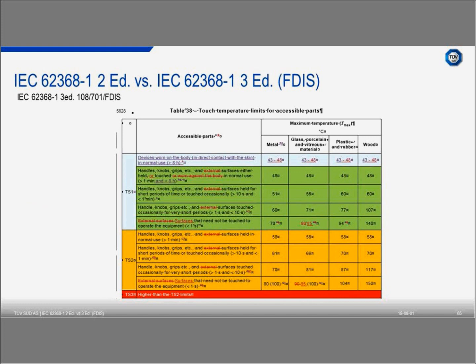For a device worn on the body, in direct contact with the skin, we make a distinction for very long-term contact, meaning 8 hours or more, where we have to go for a temperature not higher than 43 degrees Celsius. If it's for shorter contact times, then we can go up to 48 degrees. So this is now described in this table for such temperatures for devices worn on the body.